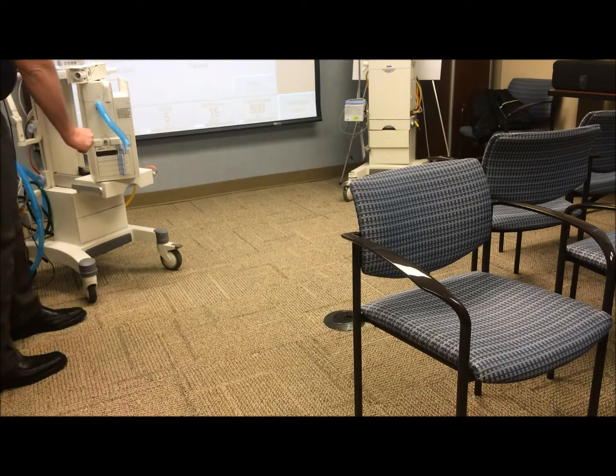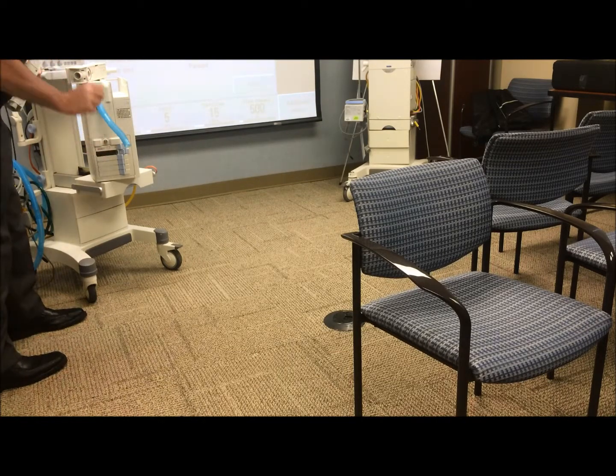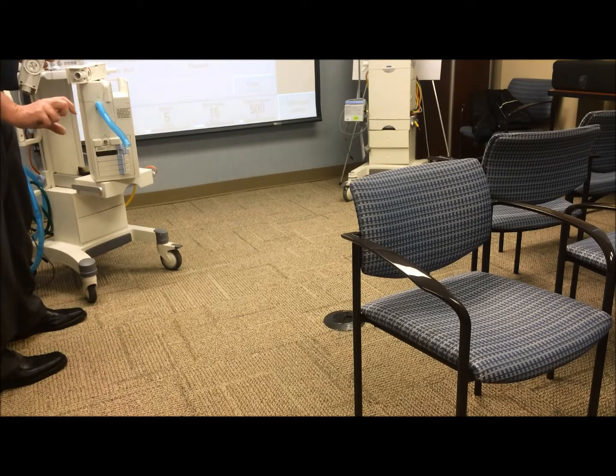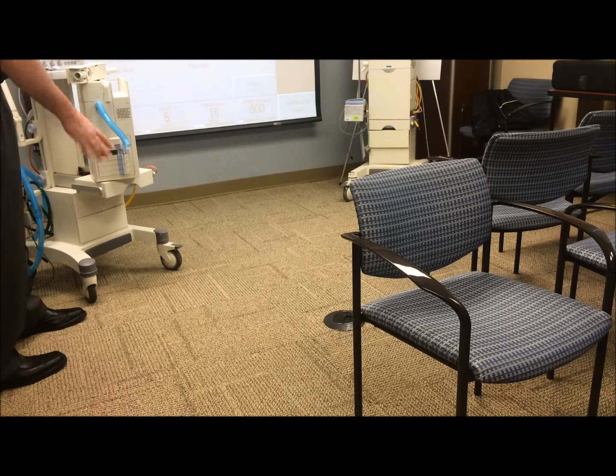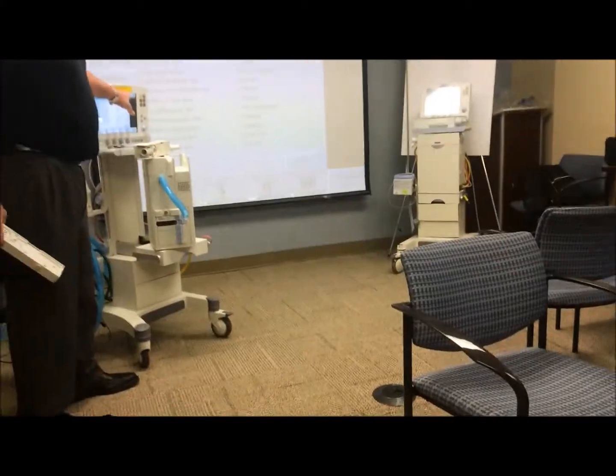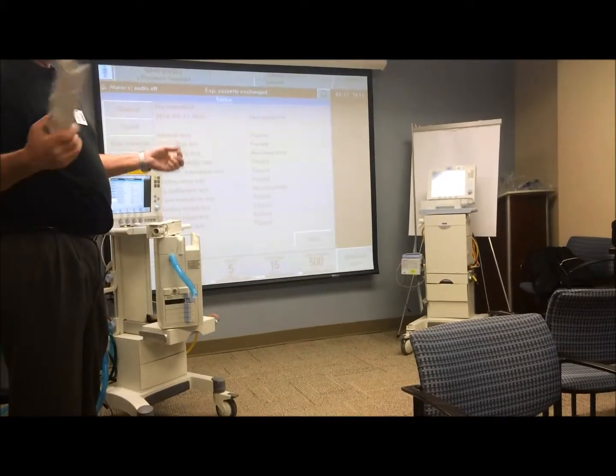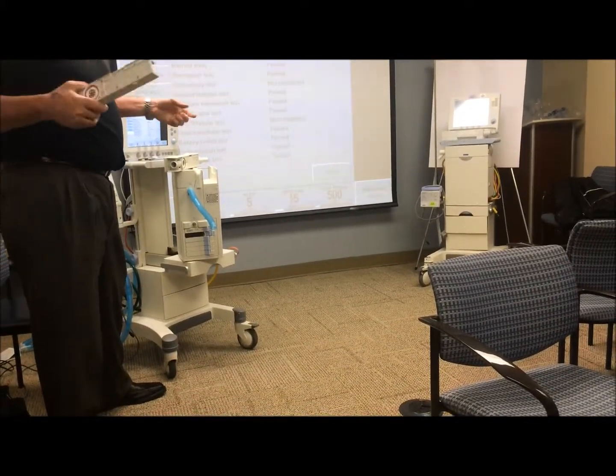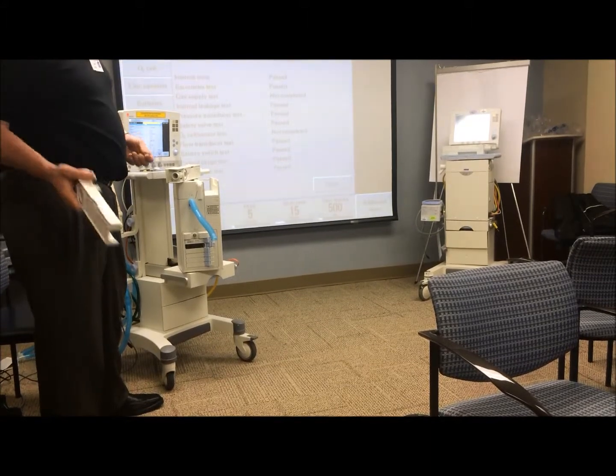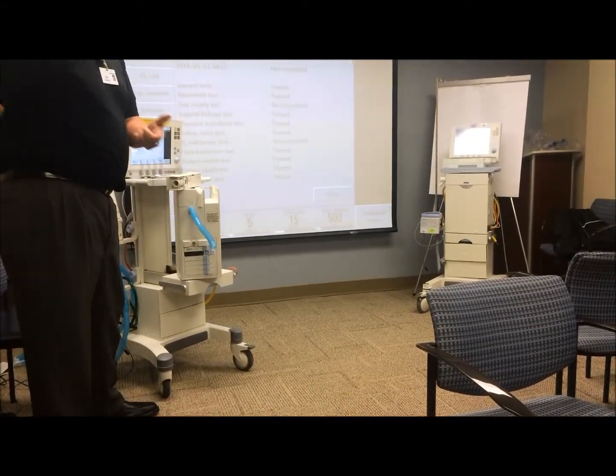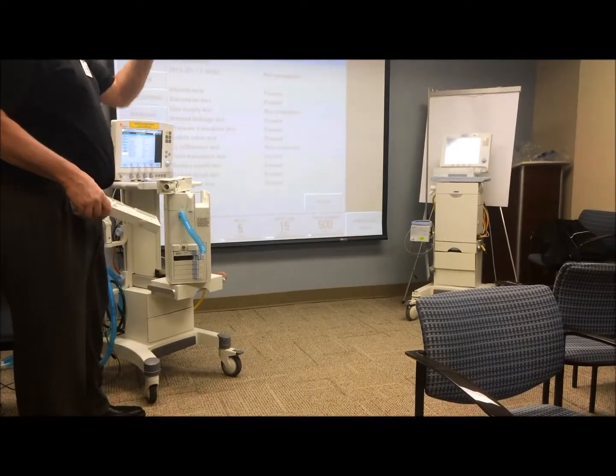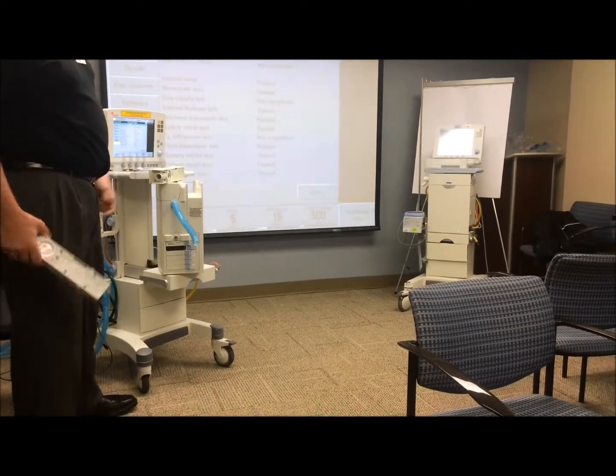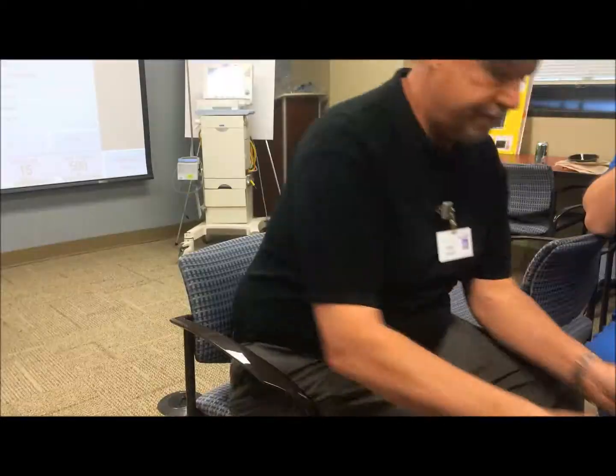And then you take that ultrasonic cable, not the ultrasonic, but the cable, and plug it into the Solo nebulizer, the disposable nebulizer. Squirt your medicine in there and put it anywhere you want in the circuit. And then up here, there's a button that says nebulizer. You just touch it and you can say, I want to deliver it for 10 minutes, 15, half an hour, or you can do continuous. Or if you're going to do Flolan, you just press this button and you're doing Flolan, and you can hook up an IV pump to drip in so much Flolan and do it continuous.